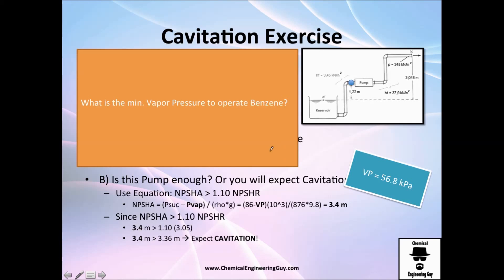One last exercise: What is the minimum vapor pressure to operate benzene? Recall that for benzene we got a vapor pressure of, we don't know it, that's what actually we want to know. But we got the density, yes. The gravity, yes. The suction line, yes. This is constant. And we know that the minimum that we need to have is 3.36, which rounding up is 3.4 meters. So this will be the minimum. We just need to solve for vapor pressure. And solving for vapor pressure, I got that the minimum vapor pressure you need is 56.8.